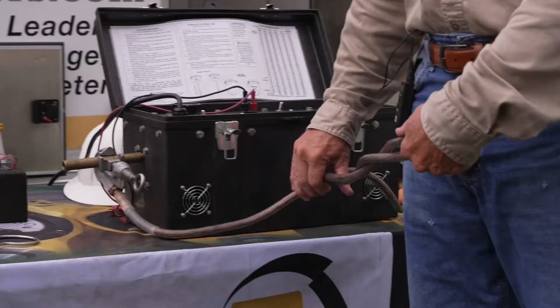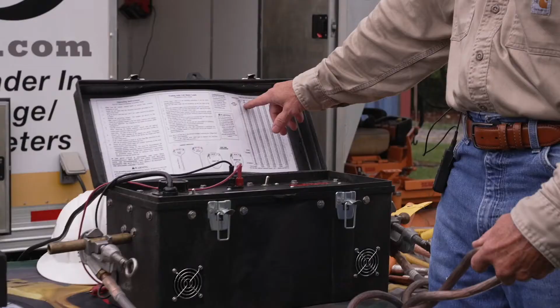So we suggest building a 2x12 channel with 2x4s on the side, pre-measured for whatever apparatus you're testing from. We don't have that here, so we're just going to mimic that parallel situation, and run this up to what's required on a number 2 cable—which we suggest be a 1/0 or 2/0, since it's not as flimsy and the odds of breaking strands inside that jacket are a lot less.